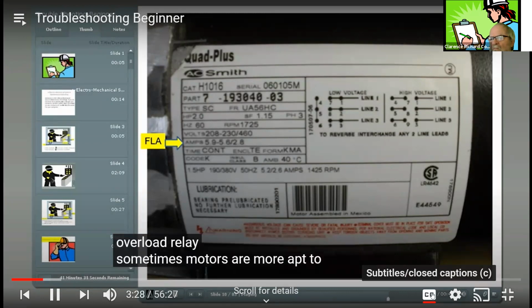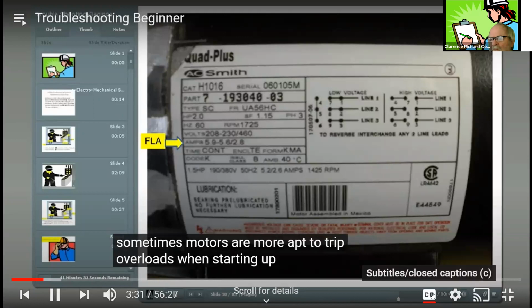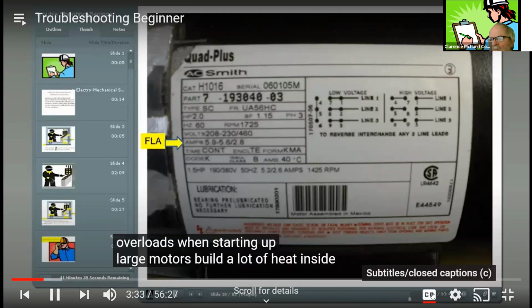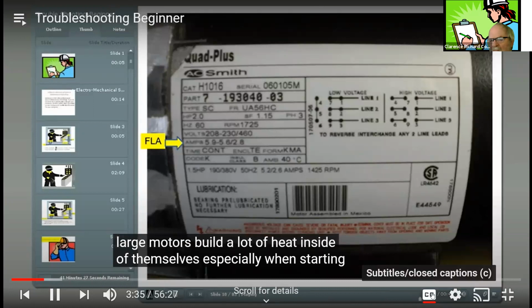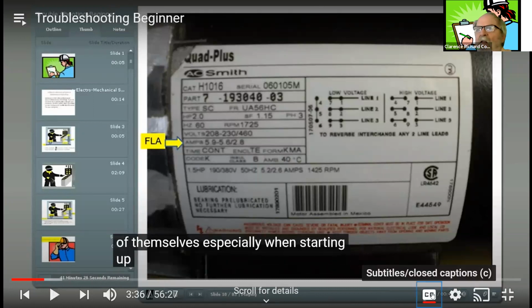Sometimes motors are more apt to trip overloads when starting up. Large motors build a lot of heat inside of themselves, especially when starting up. Let's see what this motor here has to say. It tells you some information. One is it gives you a frame size. So if you're going to be replacing a motor, you want to do it with the same frame size. So that's some information they're going to want to know.